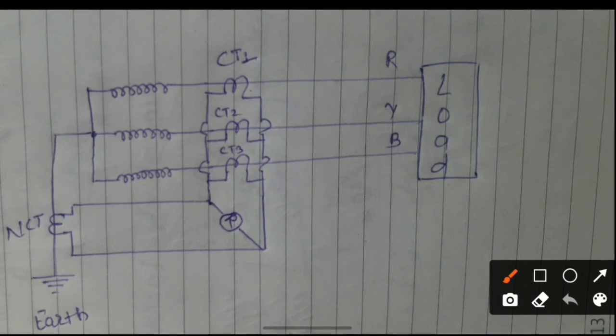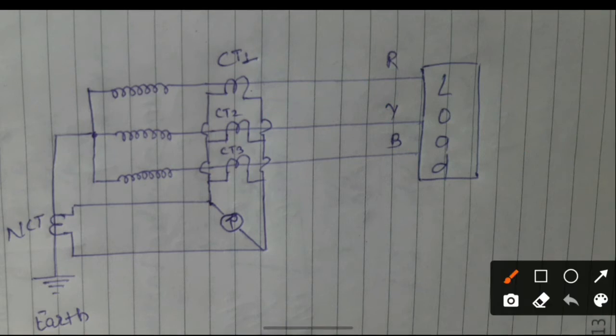In this image we can see the star winding of the transformer, which is the secondary winding. The load is connected. These are the R, Y, B phases. CT1, CT2, CT3 are shown, along with the overcurrent relay, the NCT, earth, and zero potential. We have two conditions: condition one — if the fault occurred outside the zone — and condition two — if the fault occurred inside the zone.